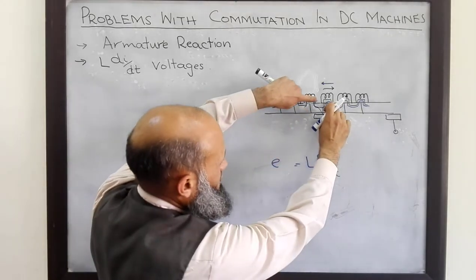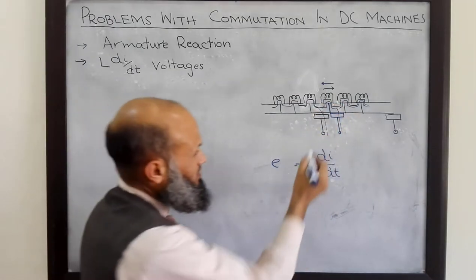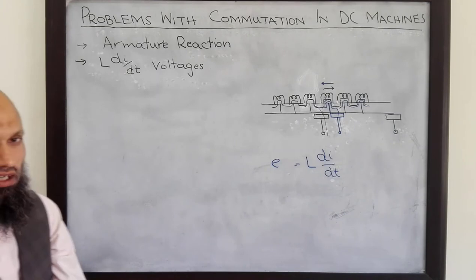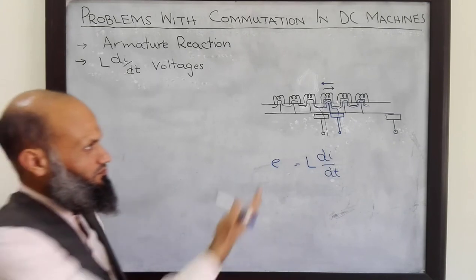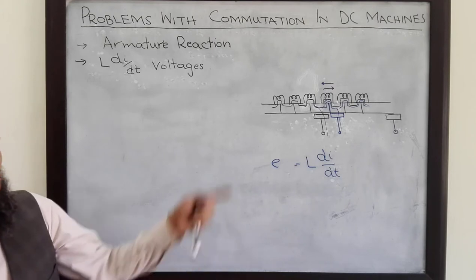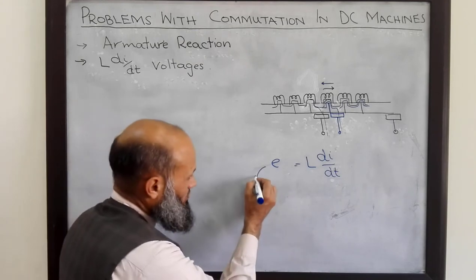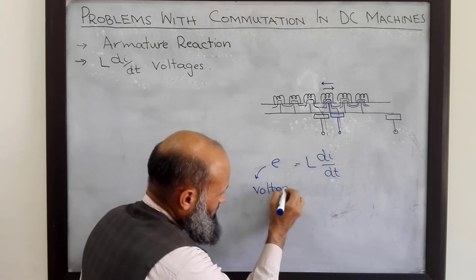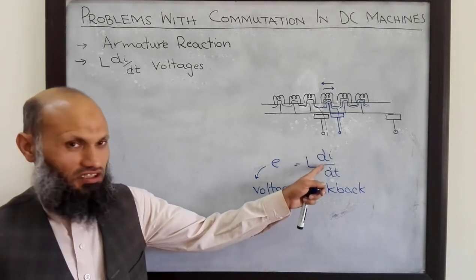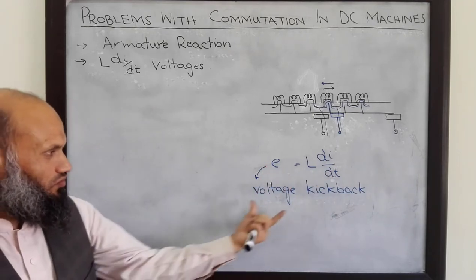Across the two ends of this inductor there will be high voltage. Although the two commutator segments are electrically isolated, due to high voltages there will be sparking between the two commutator segments. That sparking will deteriorate the commutator segments and will result in inefficiency of the machine as well as physical deterioration. This high voltage is also called voltage kickback — it is always present whenever there is a rate of change of current in an inductor. Such a change in current produces a voltage across the inductor, and that voltage is called voltage kickback.